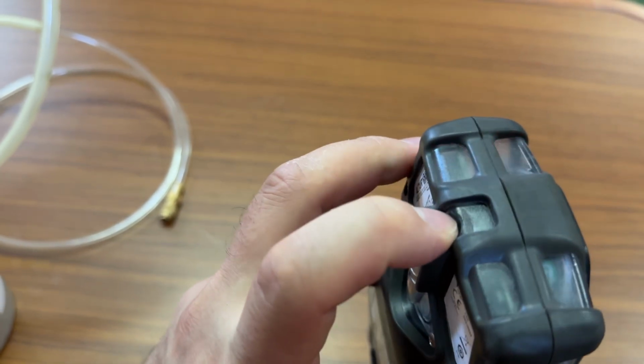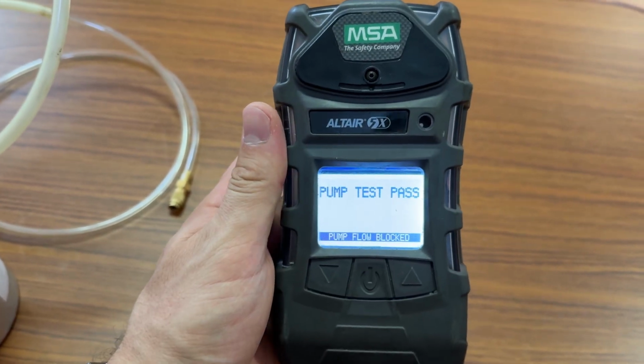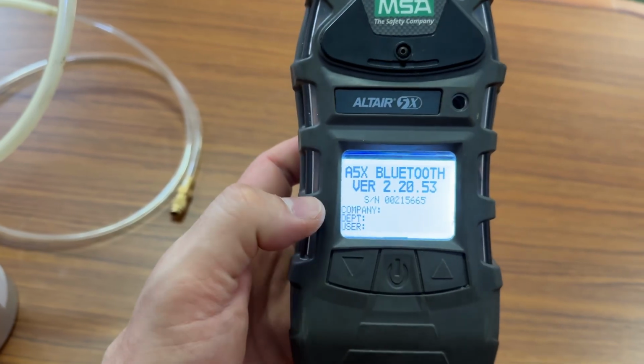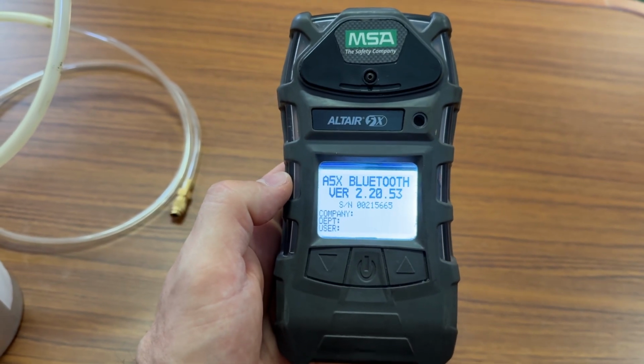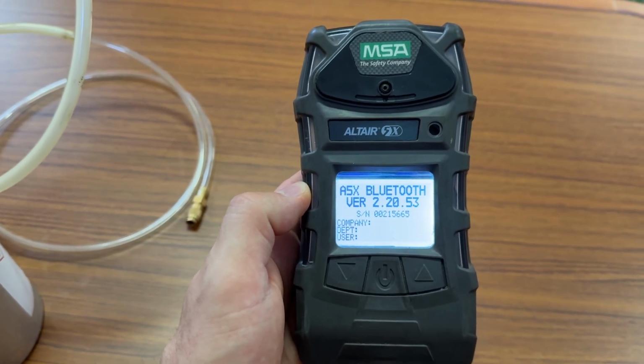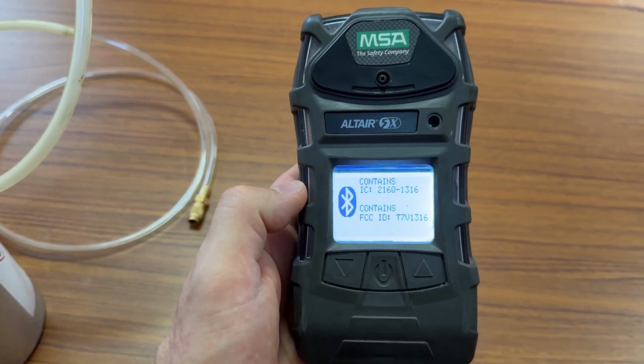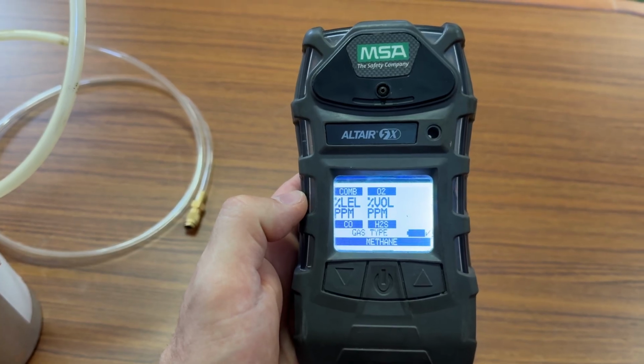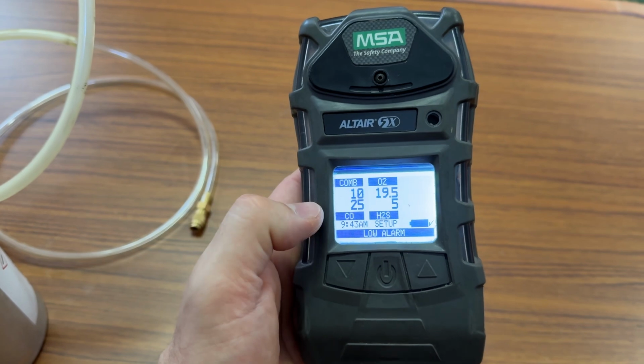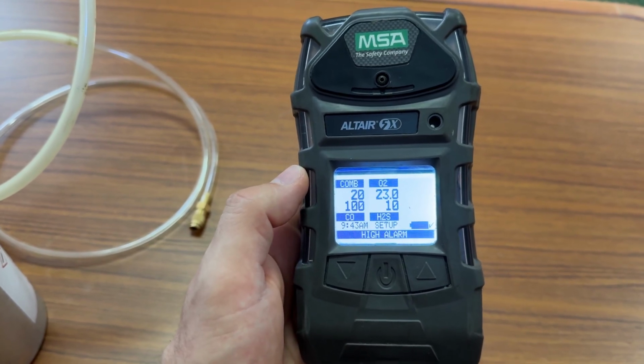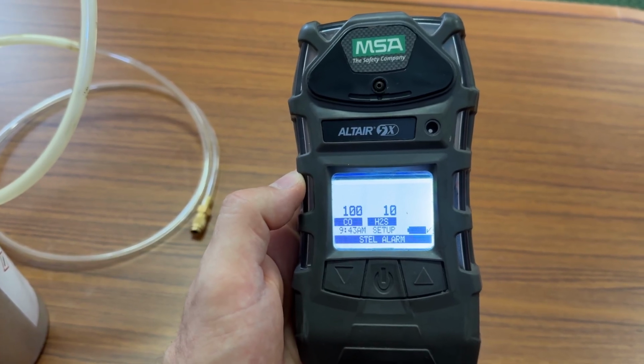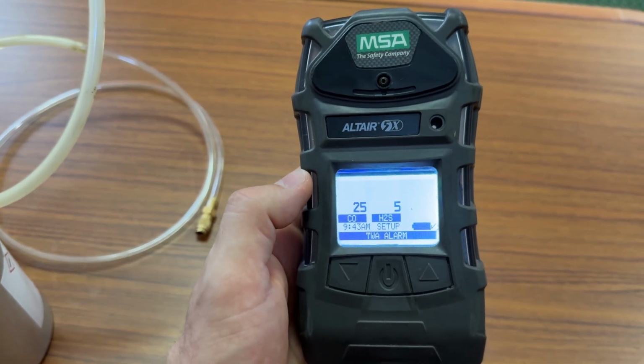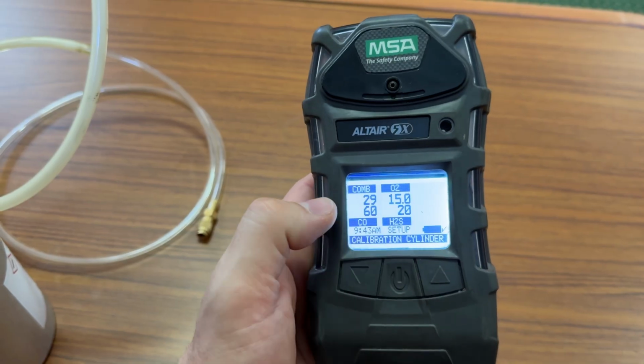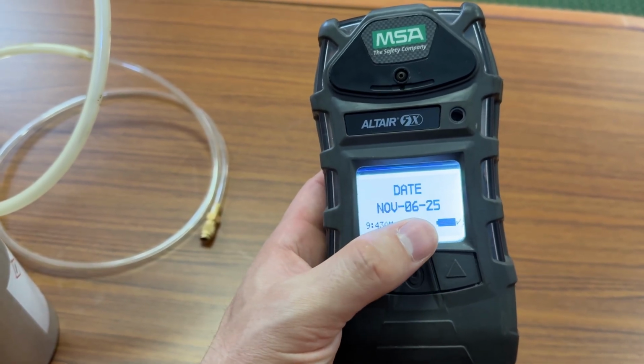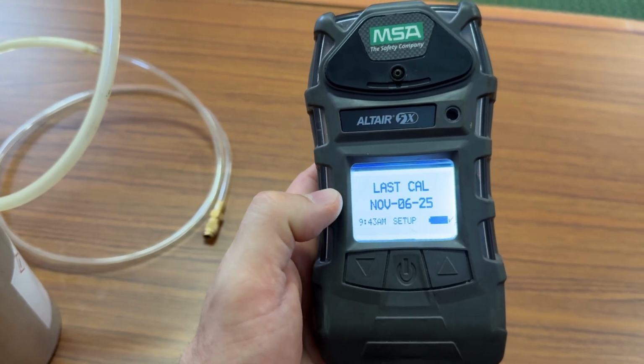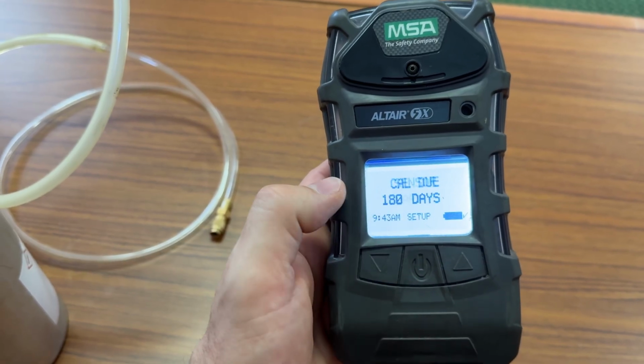Okay, pump test. Just block this second pipe. Pump test pass. And now we will see our date should be updated. Just waiting for loading all this information. It will show again for us low alarm values, high alarm, and now we show the date. Okay, this calibration cylinder. Okay, date 06 November 2025. Today is 6th of November 2025. So you see this updated: 180 days for the next calibration.